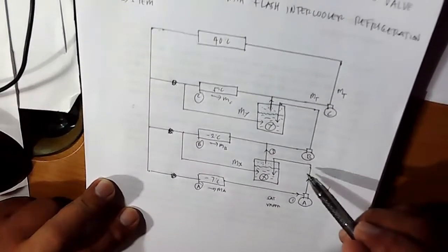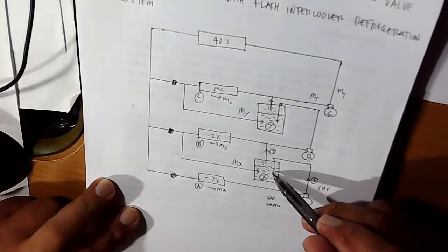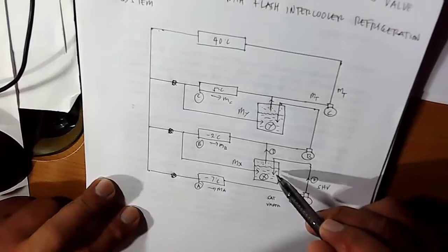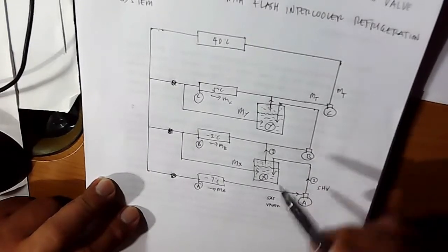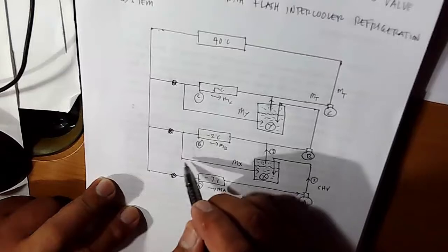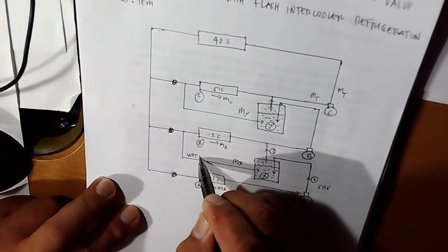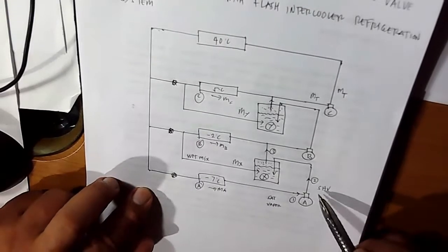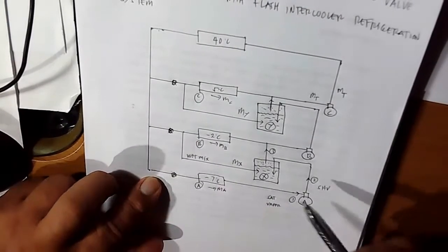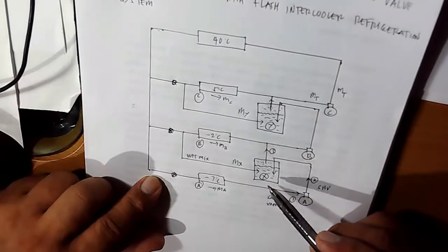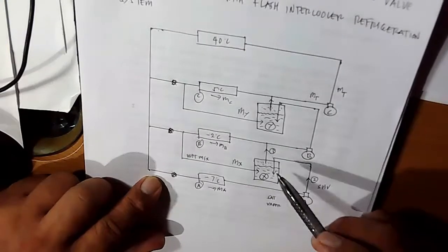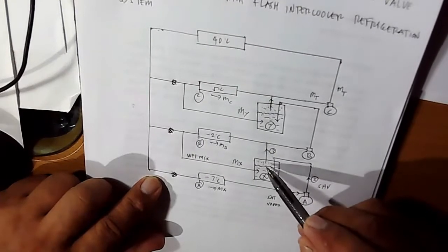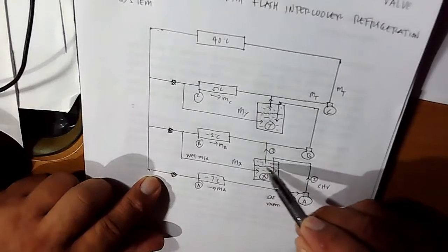When the superheated vapor refrigerant enters your intercooler X, it is submerged in the liquid. Somewhere along this point is wet mixture. So the combination of superheated vapor and the wet mixture enters in your intercooler X. Then all liquid settle at the bottom because it has weight, and it allows only saturated vapor to go up.